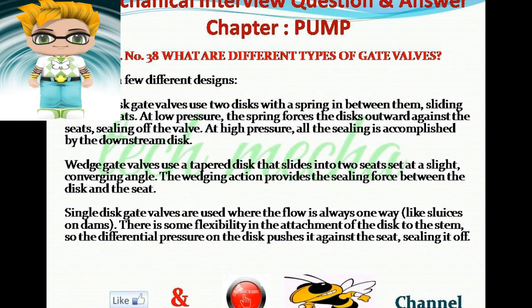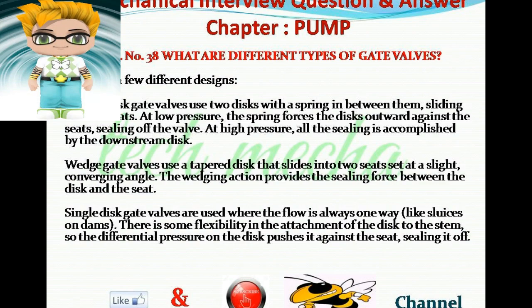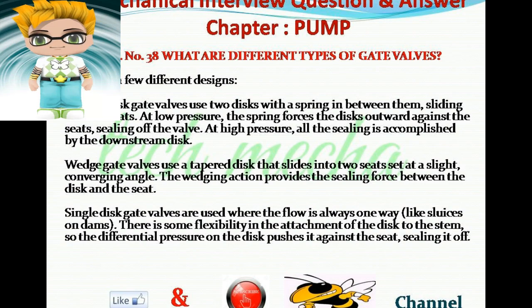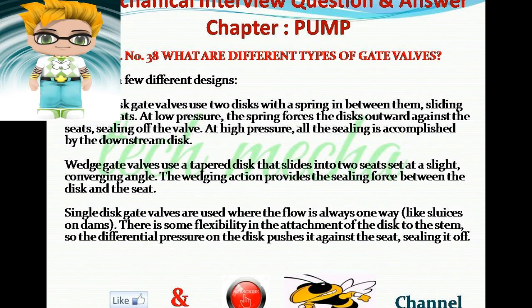Question number 38: What are the different types of gate valves? Answer: There are a few different designs. Parallel disc gate valves use two discs with a spring in between them sliding into the seats. At low pressure, the spring forces the discs outward against the seats, sealing off the valve. At high pressure, all the sealing is accomplished by the downstream disc. Wedge gate valves use a tapered disc that slides into two seats set at a slight converging angle; the wedging action provides the sealing force between the disc and the seat. Single disc gate valves are used where flow is always one way, like sluices on dams; differential pressure on the disc pushes it against the seat, sealing it off.